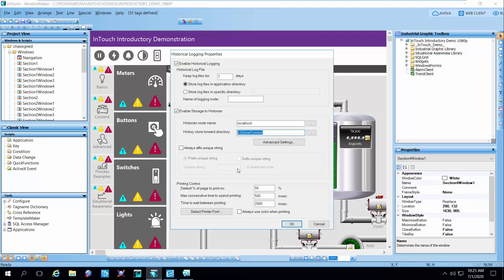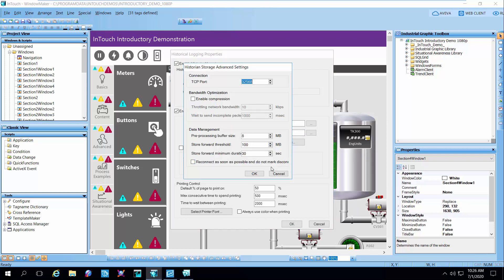We have to give it a store and forward directory — that's the place that's going to buffer the data if we lose that connection to the historian, so it'll basically catch up after the fact. There are some advanced settings here as well. This has to do with if you're going into store and forward mode — basically what we don't want is the system to start flooding the network with the backfilling of the data. We want to dribble that data across while it's getting the new information, so this controls how much data and the store and forward threshold and the minimum time that goes into store and forward mode.